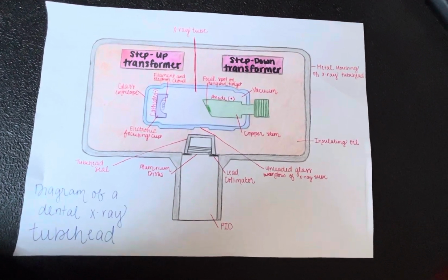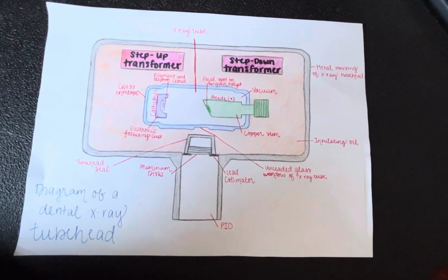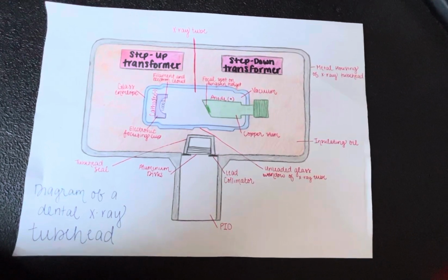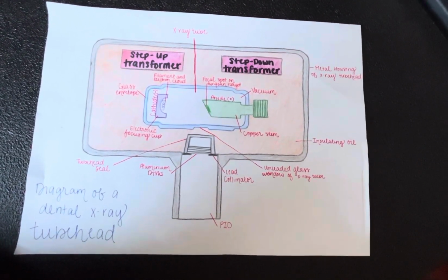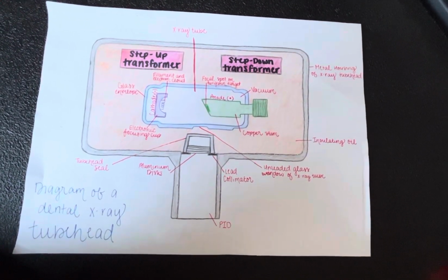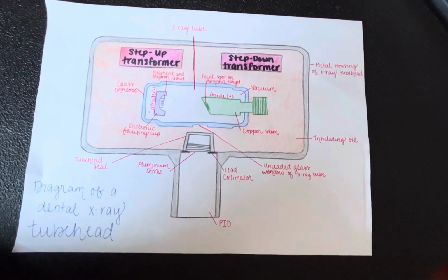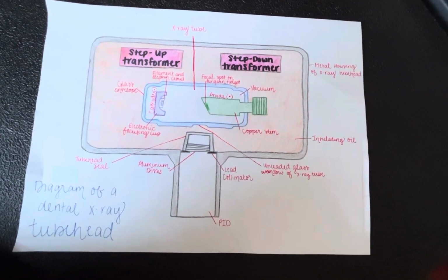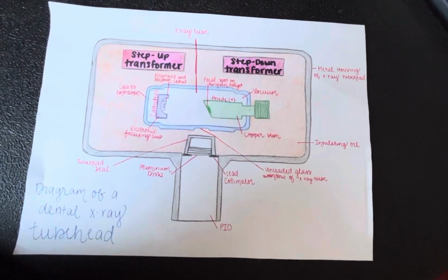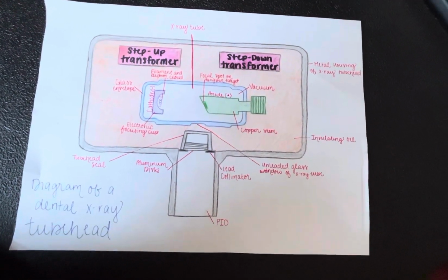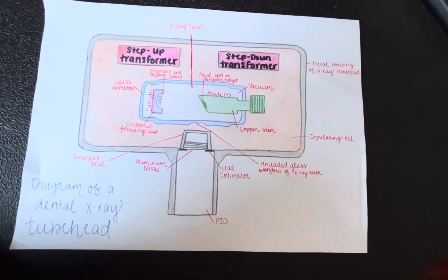The X-ray machine also contains a control panel that is used to adjust different settings in order to take radiographs, and the extension arm, which is used to move the tube head around into the correct position for taking radiographs. The tube head is a tightly sealed, heavy metal housing that contains the X-ray tube and produces dental X-rays. Let's go over the different components of the tube head.